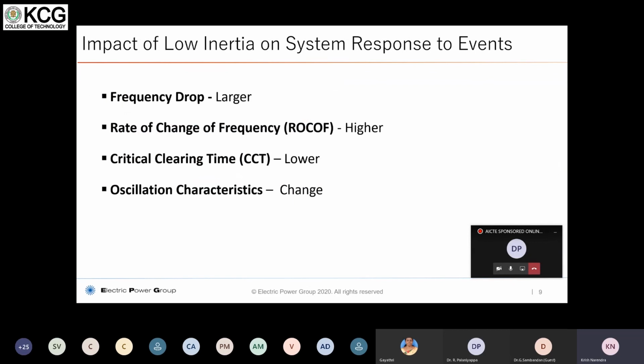So coming to the four important metrics of impact of low inertia in the system, they are as follows. The first important thing is the frequency drop. Why the frequency drops, as I told you: when the generation goes out, you're not supporting enough load. Since the system is synchronously connected, every generator tries to adjust its speed in such a way that it tries to meet the loss of generation with the same amount of load that is there in the grid, and hence the only physical phenomenon that can happen is the slowing down of the generation. So therefore the frequency must drop.